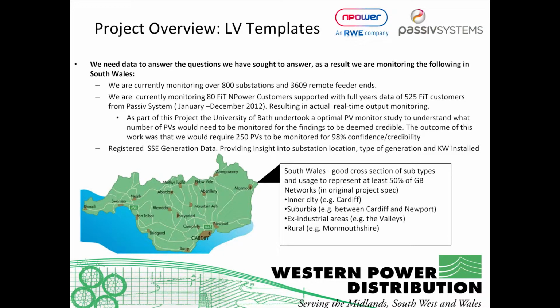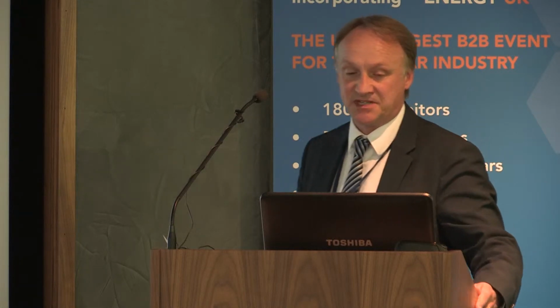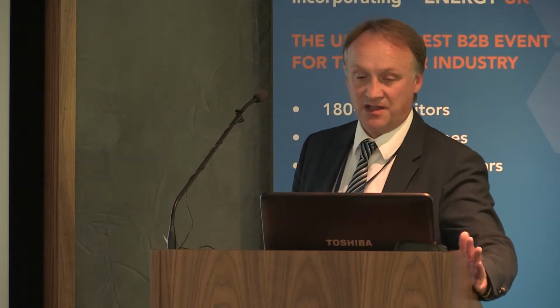We'll start with the LV templates project. We're currently monitoring 800 substations and over 3,600 remote feeder ends throughout South Wales. We're capturing 13 channels in each substation: 3 voltage, 3 current, 3 total harmonic distortion, real power delivered, real power received, and reactive power lagging and leading.